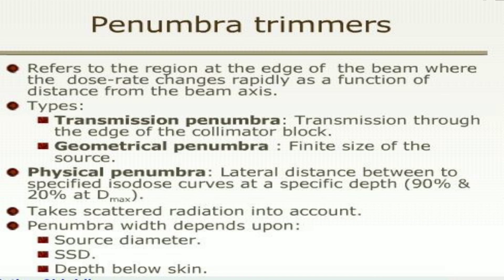Penumbra trimmer refers to the region at the edge of the beam where the dose rate changes rapidly as a function of distance from the beam axis. Types include: transmission penumbra — transmission through the edges of the collimator blocks; geometric penumbra — due to the finite size of the radiation source; and physical penumbra — the lateral distance between two specified isodose curves at a specific depth, typically 90% and 20% of Dmax. Penumbra depends upon source diameter, SSD, and depth below skin.